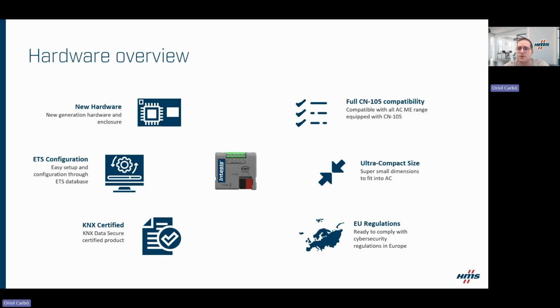So let's take a quick look at the hardware behind these new KNX Secure Gateways. This is a new generation device with a new enclosure designed to make installation easier and to fit directly inside the AC unit thanks to its ultra-compact size, as you can see. From a commissioning point of view, configuration is done directly in the ETS using the product database, so the workflow is exactly what KNX integrators are already familiar with.